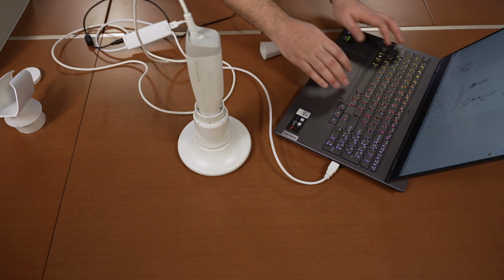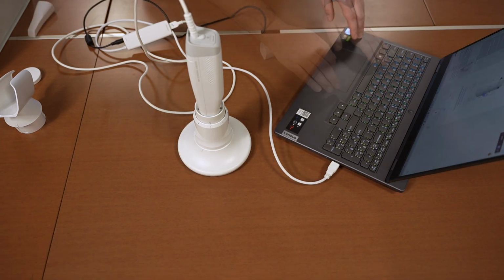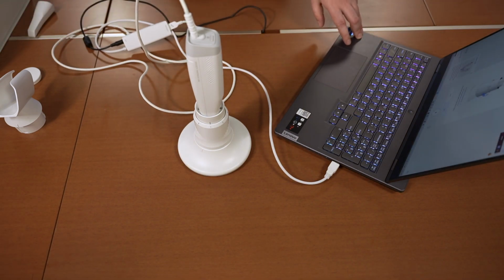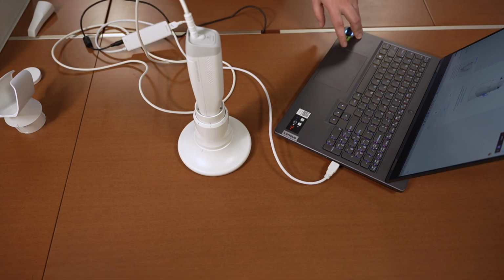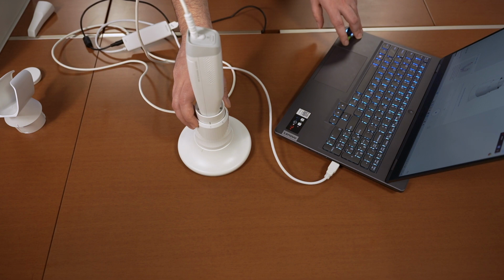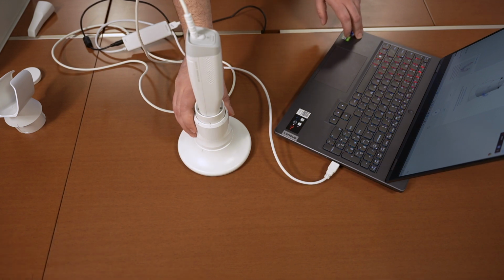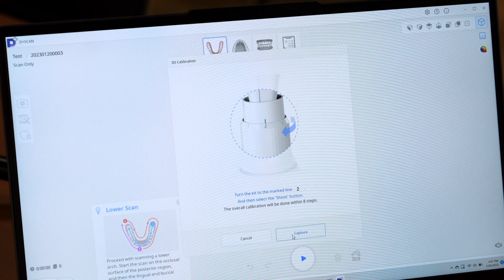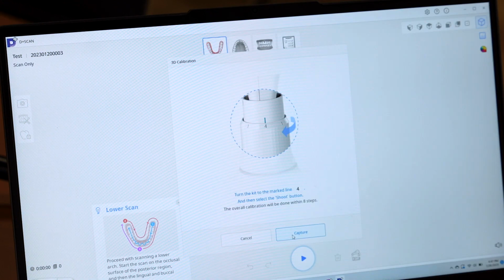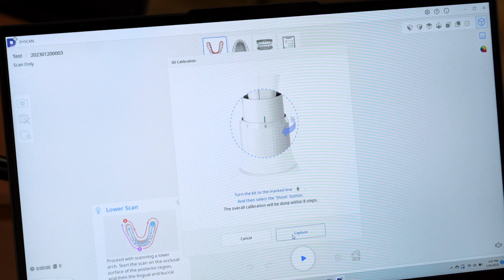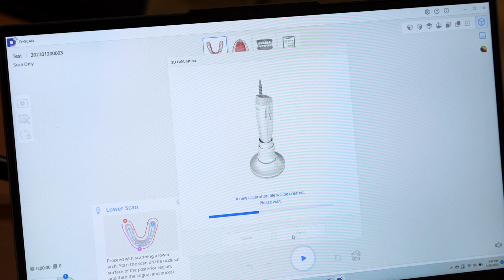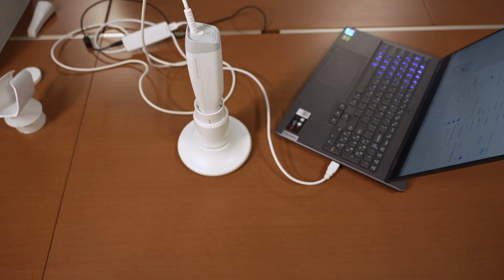Next, the computer is going to prompt you to start or begin calibration. To begin the calibration process, you would need to follow the instructions on the computer. Your line must be twisted to the next number on your calibrator and you should press OK on your computer. So slowly twist to number 2, hit OK. Slowly twist to number 3, hit OK. Now that your device is fully calibrated, you can go ahead and use your intraoral scanner.